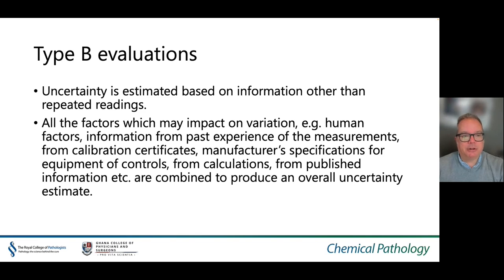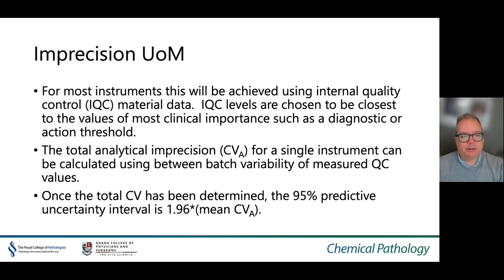This is in contrast to Type B evaluations, whereby uncertainty is estimated based on information rather than repeated readings. All factors which may impact variation — for example, human factors, information from past experience, or from calibration certificates — are combined to produce an overall uncertainty measurement. When determining imprecision uncertainty, this can be achieved using internal quality control material. IQC levels are chosen to be closest to values of most clinical importance such as diagnostic or action thresholds. Total analytical imprecision CVA for a single instrument can be calculated using the between-batch variability of a measured QC value. Once total CVA is determined, the 95% predictive uncertainty interval is 1.96 times the mean CVA.